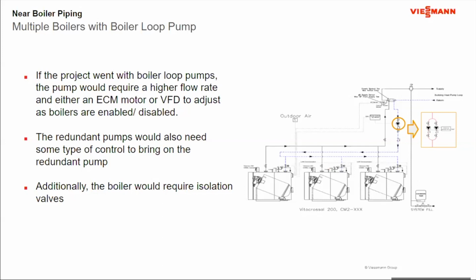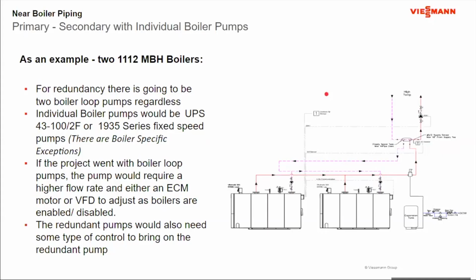Okay. Now, my other option is to go with boiler pumps. So here, each boiler gets its own individual pump. The pump is controlled by the boiler control.